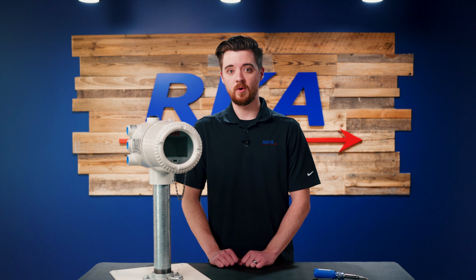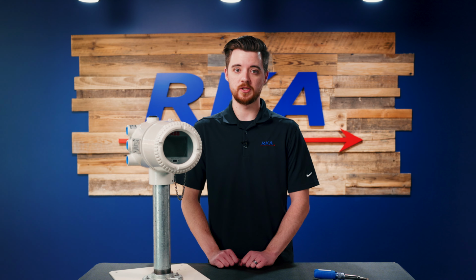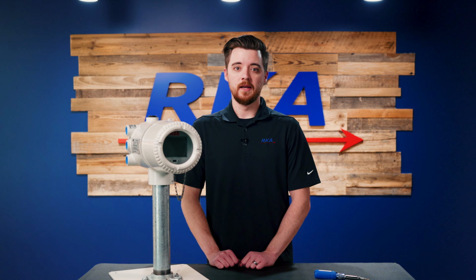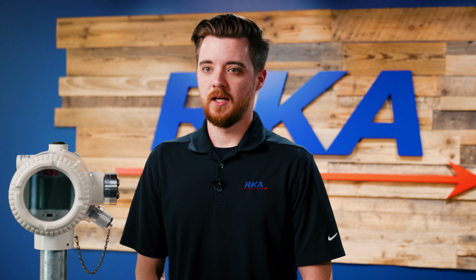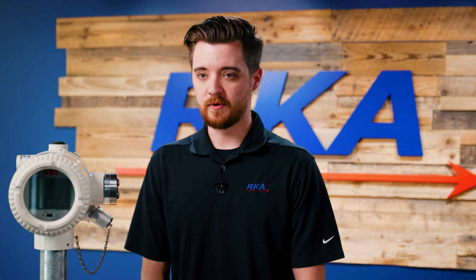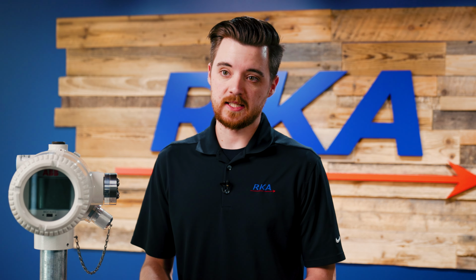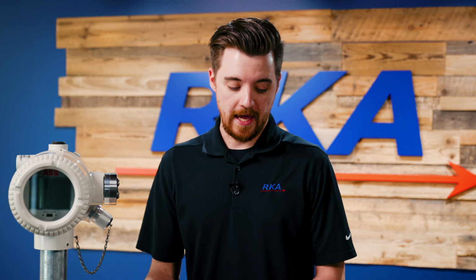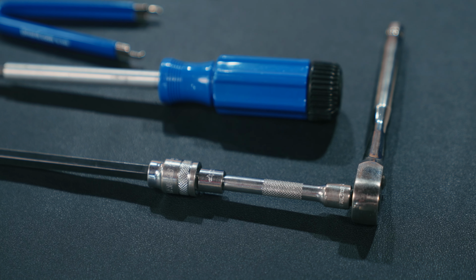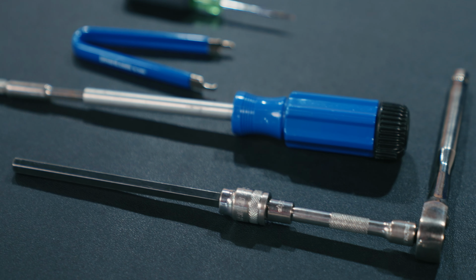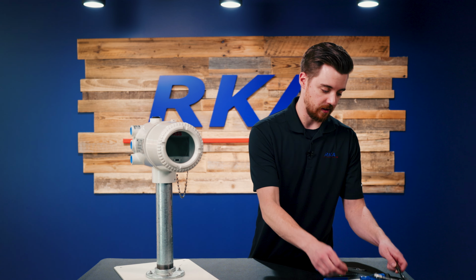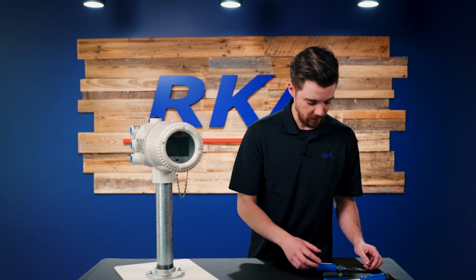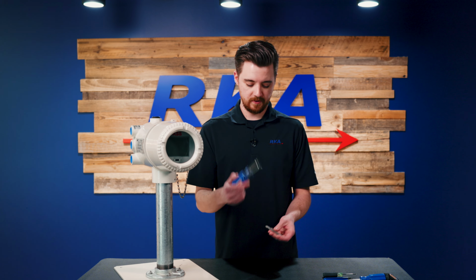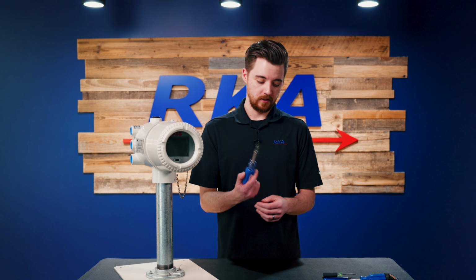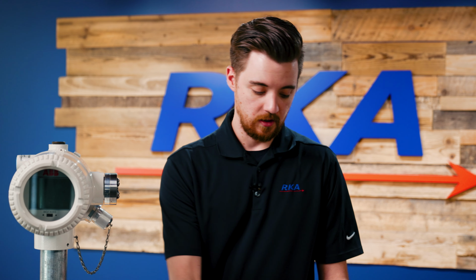In this video, we will walk through the process of replacing a GC module in an ABB natural gas chromatograph, or NGC. Before beginning the procedure, gather the tools needed: a long 5/16 Allen, which can be a screwdriver type or a socket attachment, since it needs to reach a bolt in the back of the NGC. You'll also need a 5/16 nut driver or flathead screwdriver, and a ribbon cable puller or small screwdriver.